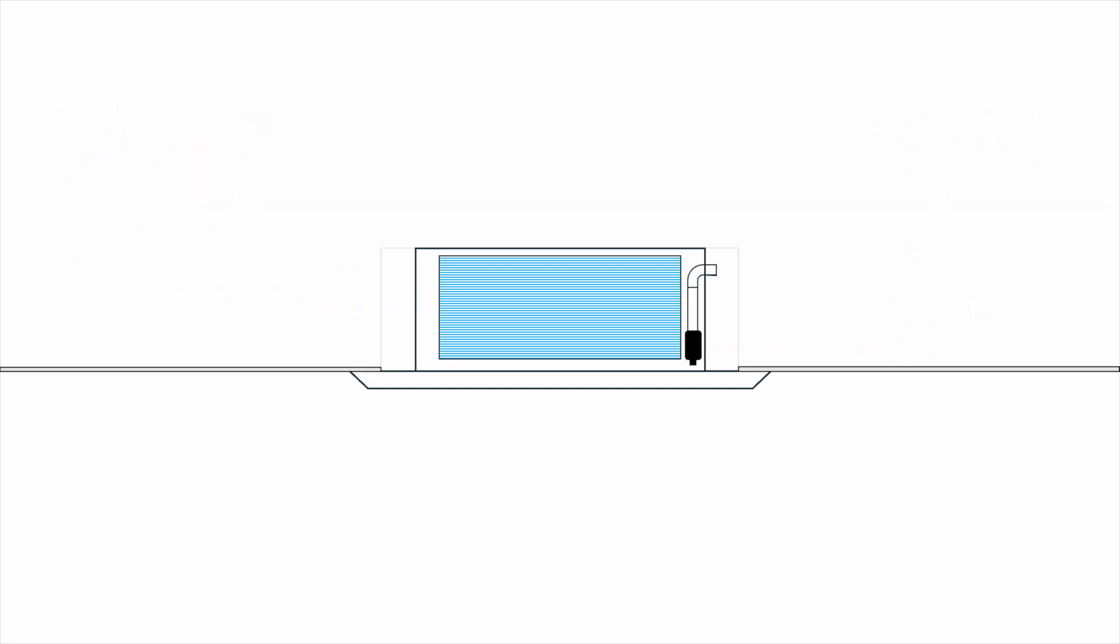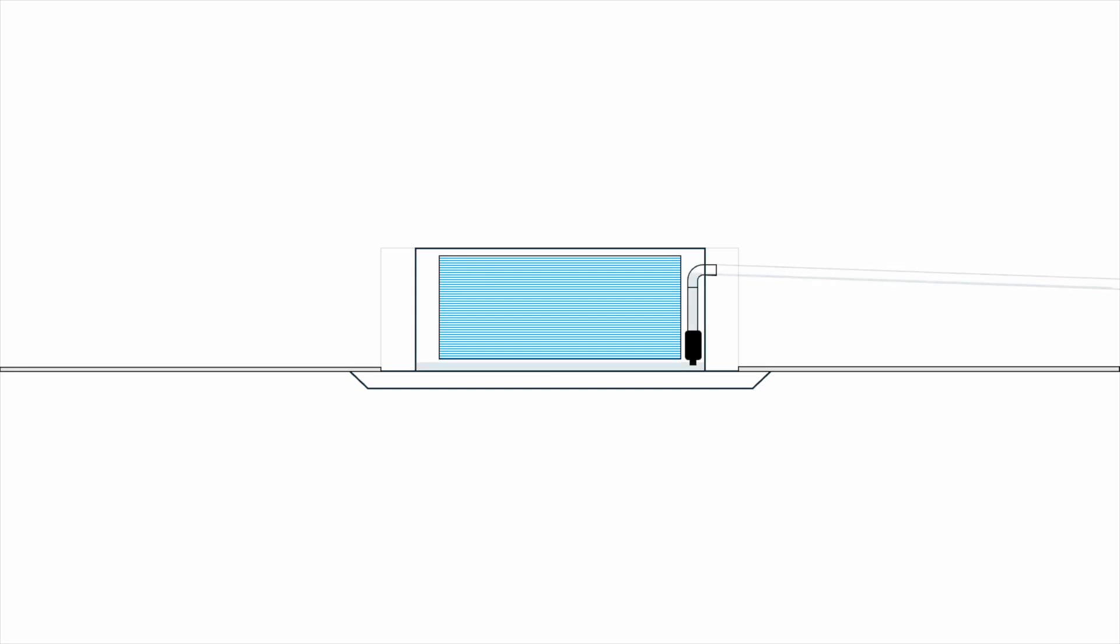During operation, condensate water forms on the cooling coil and drips down to the drain tray within the unit. When there is enough water in the tray, the drain pump will start pumping out the water. So when installing a ceiling cassette unit, we need to connect a drain pipe. There are two ways to connect the drain pipe. First is the normal way. We make sure there is enough slope for the drain water to flow properly.